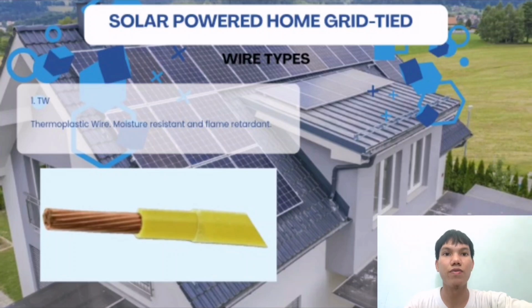Because solar installations are often exposed to the elements, wiring must be able to withstand more than just standard indoor conditions. This TW wire is designed with a specific thermoplastic insulation that makes it incredibly moisture resistant. This is vital because over time humidity or condensation inside conduit can degrade inferior wires, leading to a short circuit. Additionally, the wire is flame retardant, meaning it's engineered to resist catching fire even if there is an unexpected surge or heat buildup within the circuit.